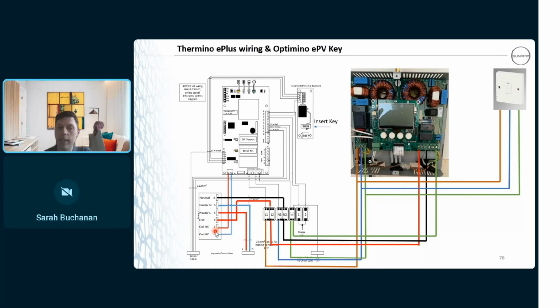That circuitry is already energized for the allowance of PV coming down your L2. So when you're talking about your hot cancel delay, if you've got a soft overheat, it's all related to the soft overheat. So if that bottom sensor reaches temperature, it will de-energize your element relay. You still want power to be going down to the relay, but you don't want the eddy to come up with that maximum temperature reached display. So that's what the hot cancel delay does.